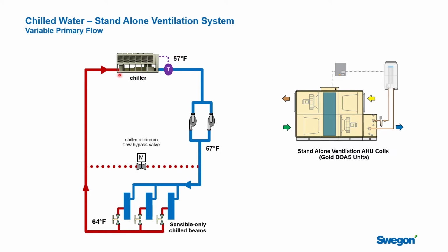You could bolt on some waterside free cooling, either having it integrated into the chillers or through a heat exchanger to the cooling towers, and take this chiller plant offline once you could produce 55-degree water from your cooling towers. So if you have a 7 or 8 degree approach on your cooling towers, you want to make 55, somewhere around 46, 47 degree wet bulb temperature outside, you would be able to produce the water that you need just using a cooling tower and shut down the chiller plants.